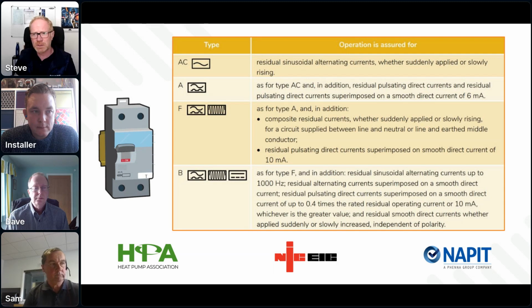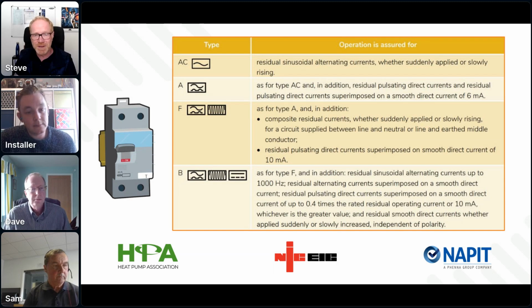We've got to get the right type of protective device for the right type of installation in any installation, not just heat pumps. So it's even more important with heat pumps being installed. Now, we've said this time and time again, this could be as simple as following manufacturer's instructions, as mentioned earlier. Could you then be going against the warranties, the small print that Dave mentioned, and some of the warranties are not valid anymore.